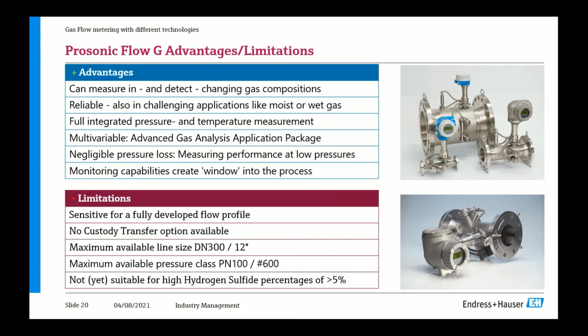So the advantage of the device: it can measure and also detect changing gas compositions. It is a reliable measurement because it can also work under challenging conditions like moist or wet gas. It has a fully integrated pressure and temperature measurement, and with fully integrated, I mean it's even embedded in the diagnostics of the device. It is in the end one instrument. Due to the fact that it measures not only flow rate, but also temperature, pressure, and speed of sound, you really have a true multivariable instrument. And those inputs are directly important for the advanced gas analysis application package, the calculation possibility I mentioned earlier.